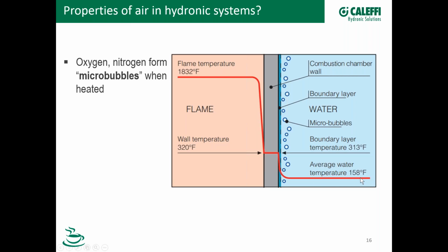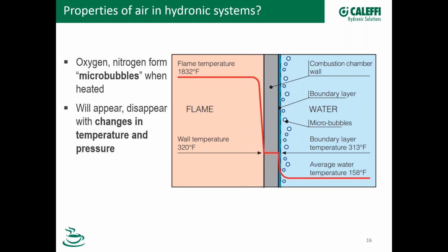So looking at this red line here, let's start at this cold, or not cold, but cooler temperature in the water in the boiler. As that water gets close to the boundary layer of this combustion wall chamber, the temperature increases significantly. So what happens is these microbubbles are formed continuously on the surface that separates the water from the combustion chamber due to this high temperature. And these bubbles are carried from the boiler to the rest of the system by the flow of the water. So these bubbles will appear and disappear with changes in temperature and pressure. So they will go, from being dissolved to being microbubbles visible, and back and forth based on the temperature and pressure of the fluid.